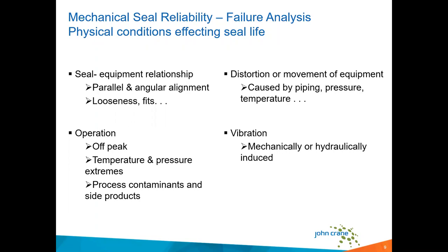So these internal alignment checks that we'll discuss a little bit need to be verified at each maintenance interval, especially when the seal is replaced. A lot of times they're not, and again, in my experience, that can really shorten the life of the seal and usually contributes in one form or another to degraded performance.